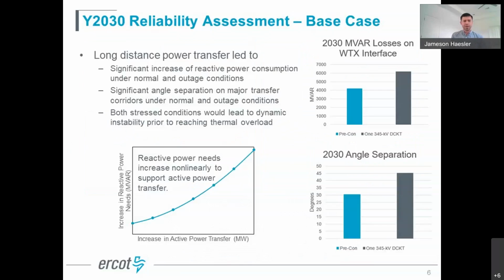So if we start taking a look at our 2030 key findings, starting with the base case from a reliability perspective, we see some problems associated with the high transfer, specifically high megavar losses across the interface. This isn't surprising given how reactive needs increase non-linearly relative to active power transfer, and the magnitude of that transfer across the West Texas interface leads to this. Teal here is our pre-contingency, and gray is under the loss of a 345 kV double circuit.